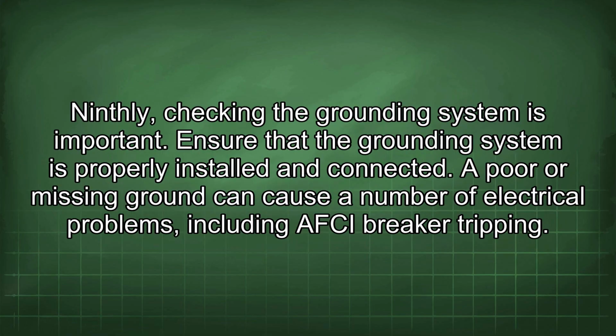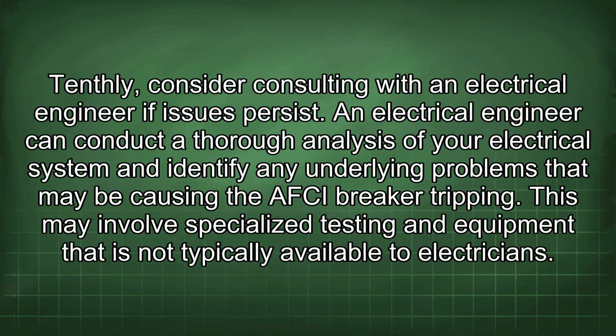Ninthly, checking the grounding system is important. Ensure that the grounding system is properly installed and connected. A poor or missing ground can cause a number of electrical problems, including AFCI breaker tripping. Tenthly, consider consulting with an electrical engineer if issues persist. An electrical engineer can conduct a thorough analysis of your electrical system and identify any underlying problems that may be causing the AFCI breaker tripping. This may involve specialized testing and equipment that is not typically available to electricians.